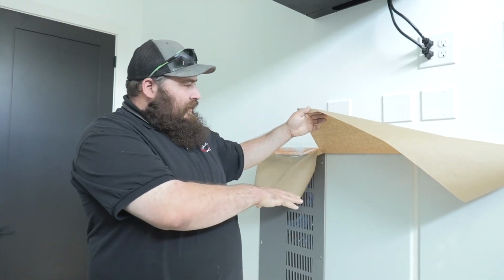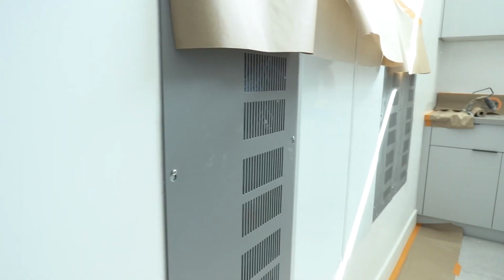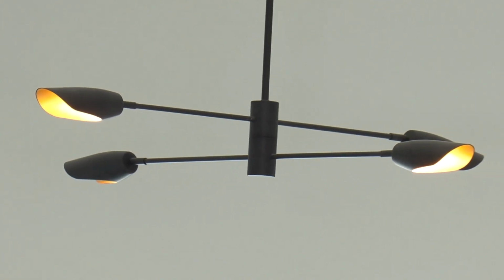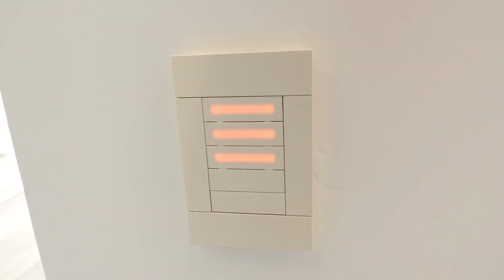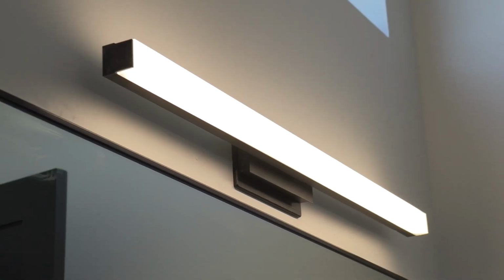So here we have our lighting control panels. In this house, all of the lighting is actually controlled through these light switches. They're all low voltage light switches that run here to control all the circuits that go out to the lighting. These are central units that bigger houses like to use. So you can do all your 120 troubleshooting from here, and you have just low volt light controls throughout the rest of the house. They have their IT cabinet up here. All their Cat 5 wires, Cat 6 wires run to this, kind of like a data room.